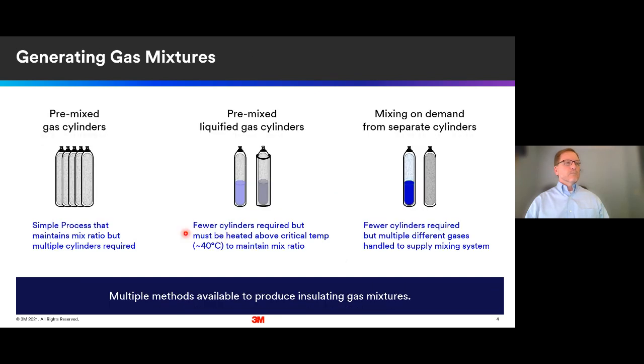So there's a number of ways that those gas mixtures can be generated. Obviously, this is a little bit different than using pure SF6, which just comes out of a single cylinder. In this case, you could pre-mix the gases. So you provide the exact gas mixture that Renee was describing would go into one of those applications. It's a simple process. It's going to function much like using pure SF6 from a cylinder. However, it's going to require a lot more material or more cylinders to fill a large piece of equipment.